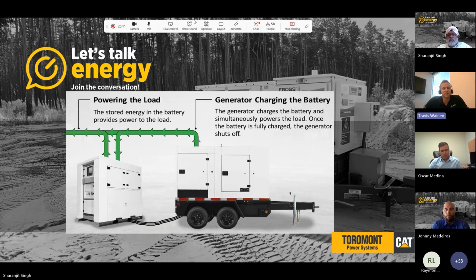This system shown is where you bring in two different assets to the job site - you roll your standard generator in, and then roll in a battery system. I call this an AC coupled system. The generator can power the load, or the battery can power the load. If the generator is running in a light load condition, the battery can run the load and then call the generator to bring it in as needed.